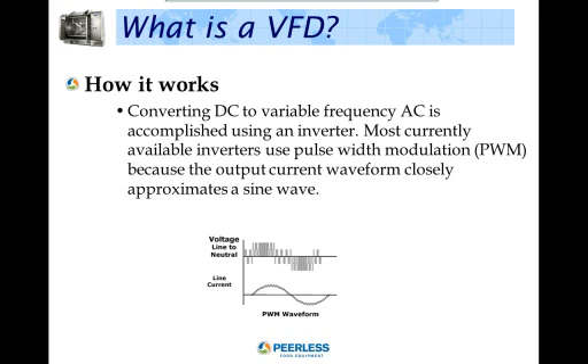The output frequency and voltage is adjusted by varying the duration of each IGBT pulse. This is where the term pulse width modulation comes from. And finally, the microprocessor interprets user commands through a keypad, input-output terminals, or communication protocols, and regulates the modulation of the IGBTs. During acceleration, the inverter applies different frequencies to the motor. It also changes the voltage, but in direct proportion to the frequency. This is known as constant volts per hertz and provides constant torque while the motor accelerates. The inverter produces rated motor torque from 0 to rated speed. It will produce full load torque while drawing much less than full load current from the power line during starting. This is due to the fact that the motor is effectively always running at speed for the applied frequency.